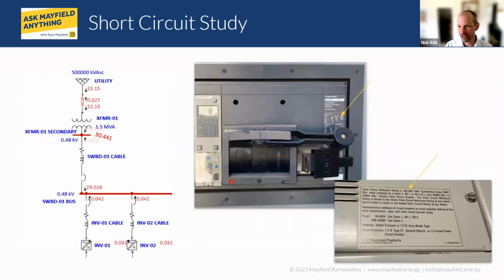Okay. The next 3 studies, as Clayton and Victor indicated, sort of relate to each other. We first, even before the thermal ampacity study, developed the ETAP single line diagram, which then later on in the course of the system design, we're getting submittals from our clients on specific equipment, such as the specific breakers, the switchgear, the transformer. We're gathering utility fault current. A lot of times the main step up transformer is going to be utility owned, and so we needed to know what primary fuse the utility was going to spec for the primary side of that transformer.